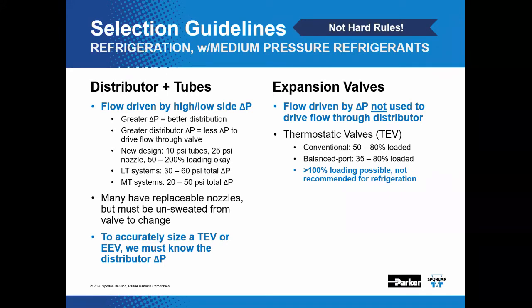Many distributors do have replaceable nozzles, but they must be unsweated from the valve to change that product. But what I want to stress here is that we must know what's going on in the distributor to accurately select the expansion valve, because flow through the expansion valve is driven by delta P that we've already used in the distributor. We'll use guidelines of 50 to 80% loading for conventional thermostatic expansion valves and 35 to 80% loading for balanced port construction thermostatic expansion valves.